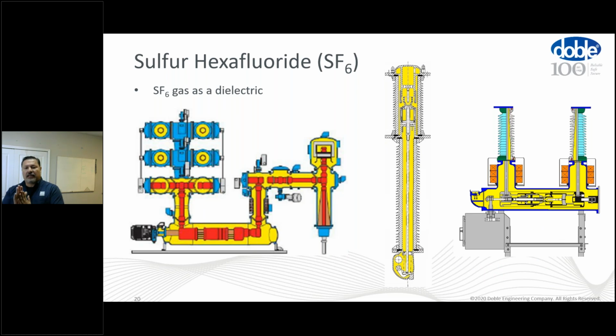Where does SF6 lie inside of high voltage or a GIE piece of equipment? As you see in the yellow, this is where SF6 would do its job. The GIE on the left is a large sample of a large GIE chamber, so throughout its chamber, allowing for a small footprint. The space that a 550 kV dead tank out in an air insulated substation would take is much larger than what a bay in a gas insulated building would be.